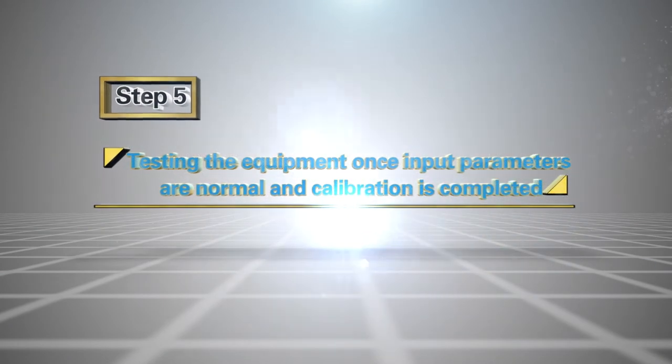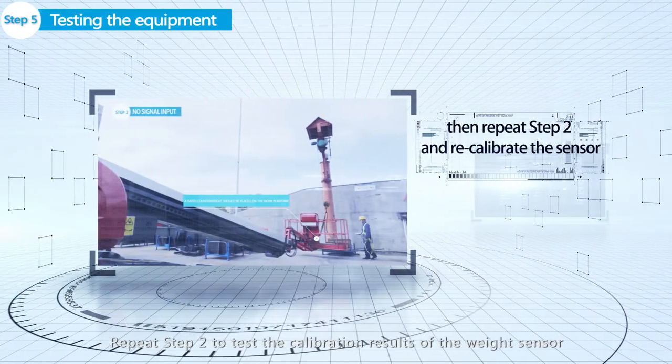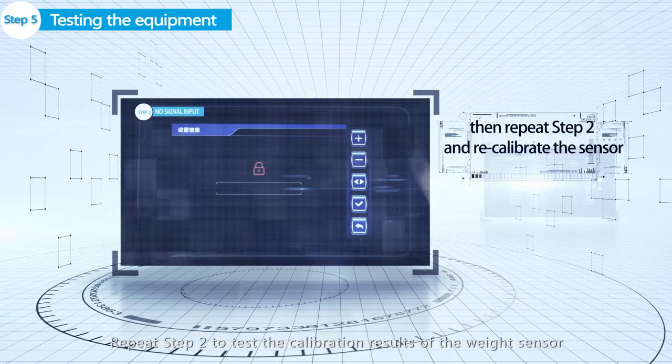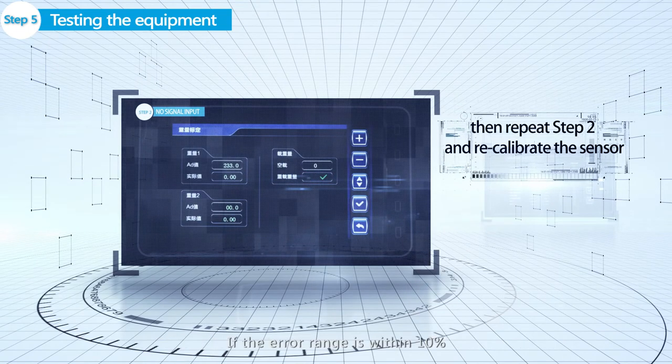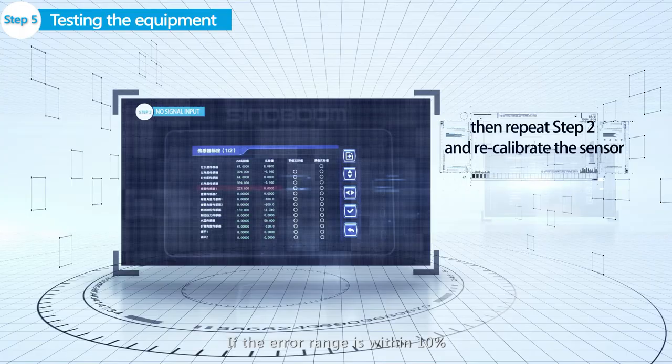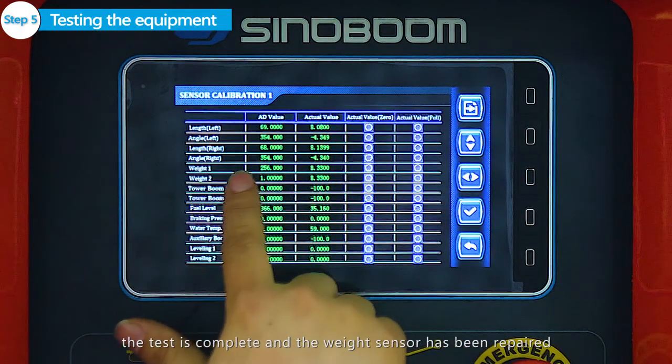Step 5: Testing the equipment. Once input parameters are normal and calibration is completed, repeat Step 2 to test the calibration results of the weight sensor. If the error range is within 10%, the test is complete and the weight sensor has been repaired.